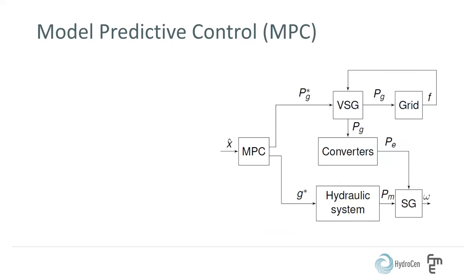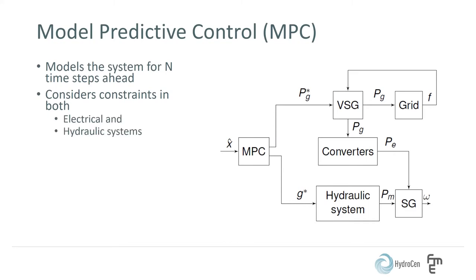Model predictive control, MPC, is utilized in this paper to optimize the control of the variable speed hydropower plant. The MPC models the system for a given number of time steps ahead to predict the system's performance. It is able to consider constraints in both electrical and the hydraulic system. With this information, the MPC optimizes the system for each time step by minimizing a defined cost function. And is thereby able to coordinate the control of the hydraulic and electric system by setting the power reference to the VSG and the guide vane opening reference to the turbine.